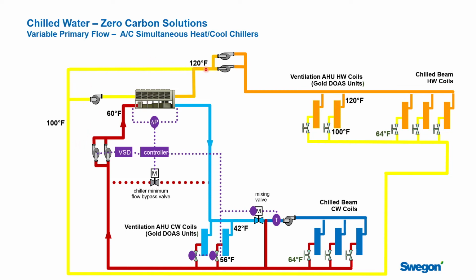And so this yellow-orange loop in here is the chilled beams and potentially the air handling units' hot water coils. And so now we're going to send out hot water somewhere between 110 and 120 degrees, which would be fine. We can heat the perimeter zones, so we could be collecting heat down here in the core, using that heat through the chiller plant to heat the outside beams. That heat would go into the air. This water is cooled down. The yellow line comes around through the pumps, and we put the heat back in to warm it back up.